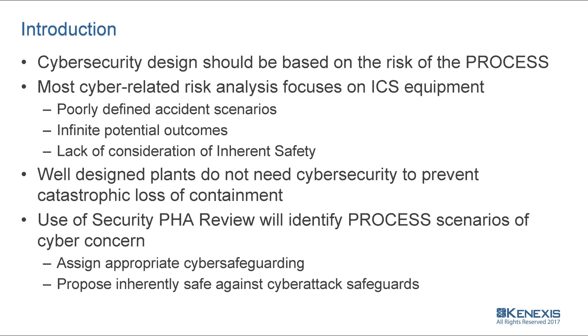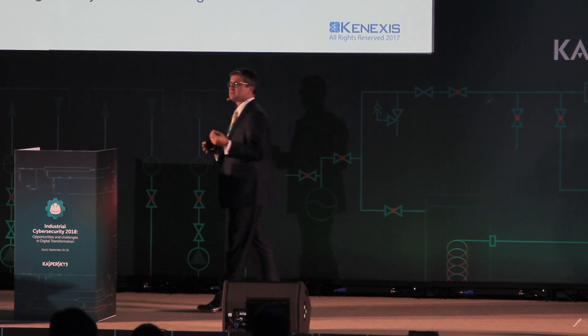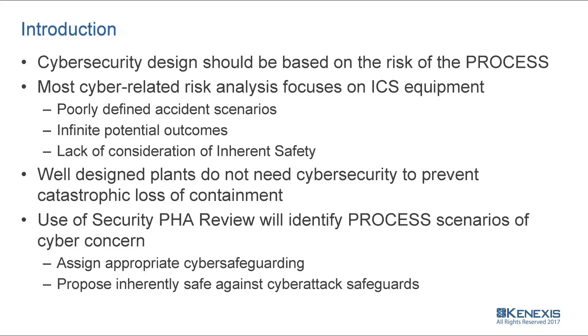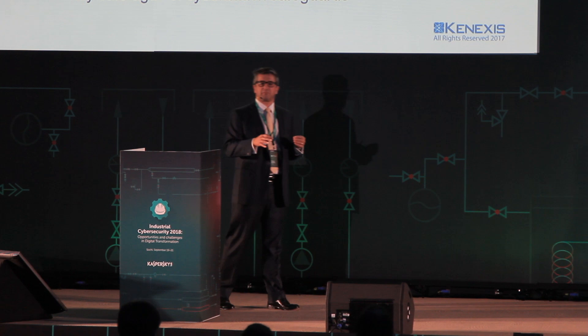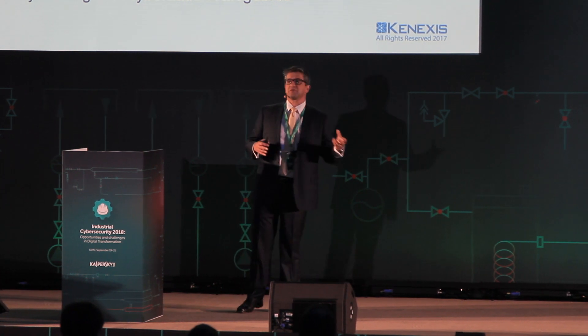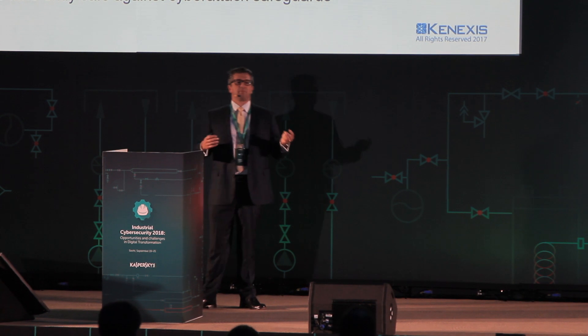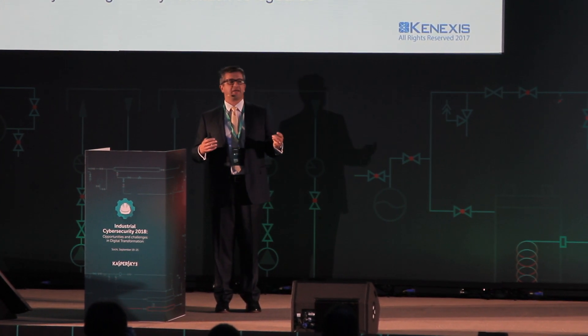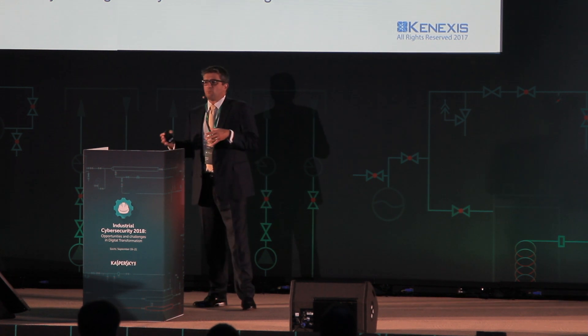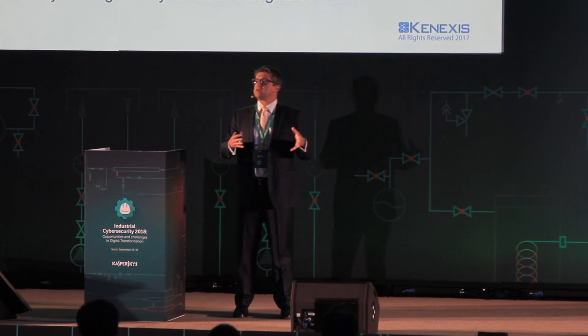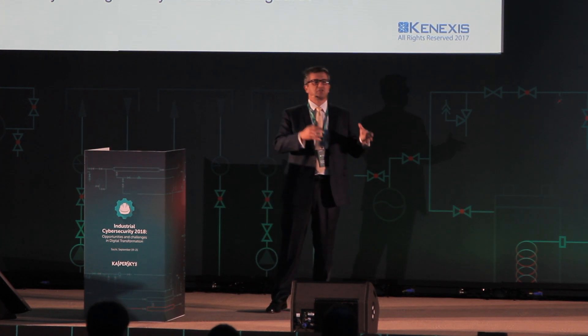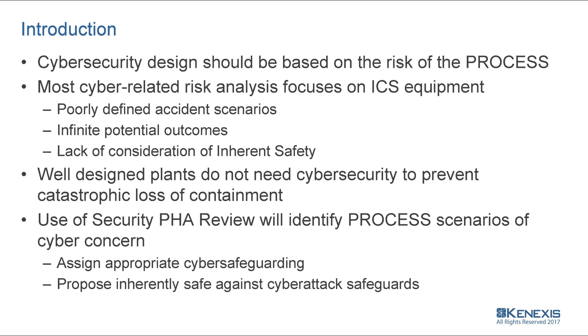The starting point is that cybersecurity should be based on the risk of the process, and we have ample experience in understanding and analyzing the risk posed by process plants. Unfortunately, most cyber risk analysis activities don't consider the process. They simply look at the industrial control system equipment — things like a cyber HAZOP, a cyber PHA, or a CHAZOP — they're essentially failure modes and effects analysis of the control equipment, but they don't tell you what happens to the process.